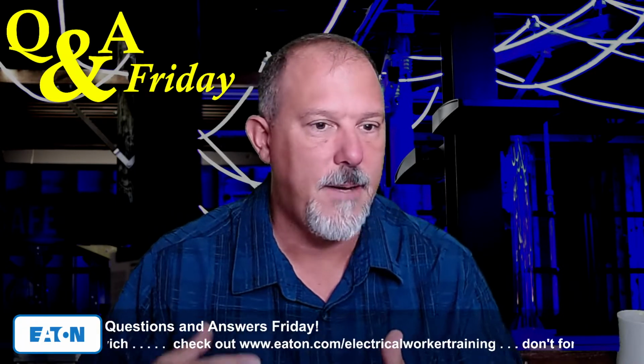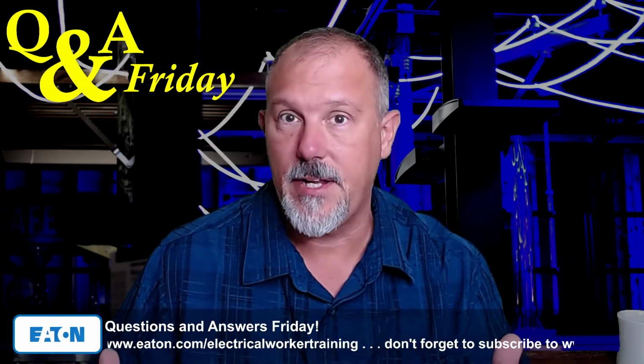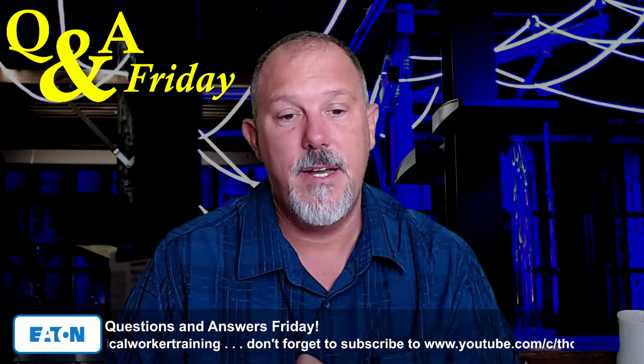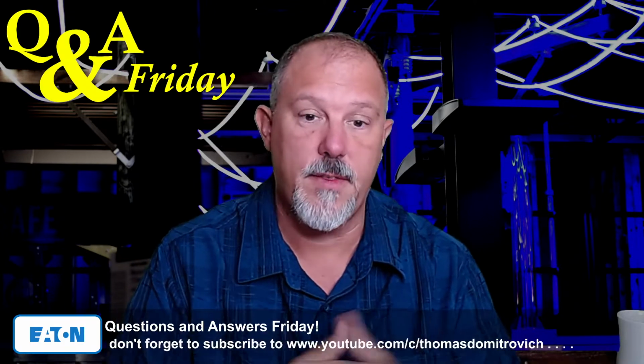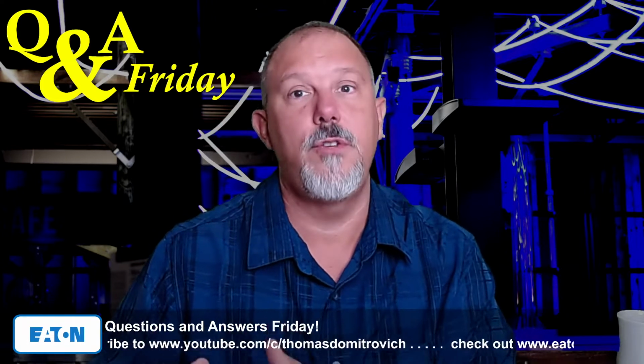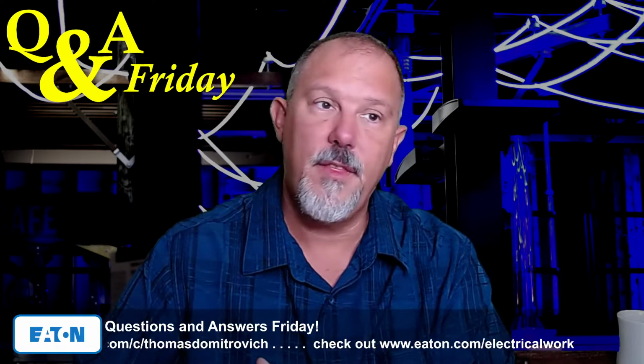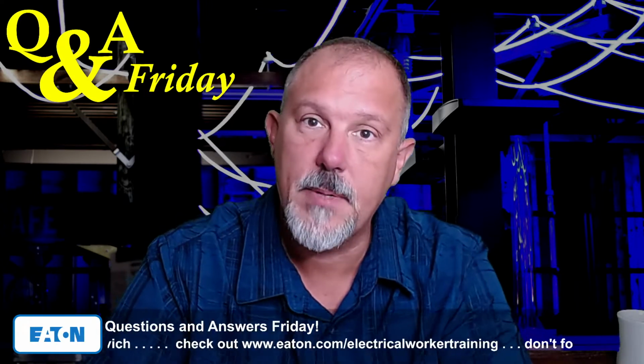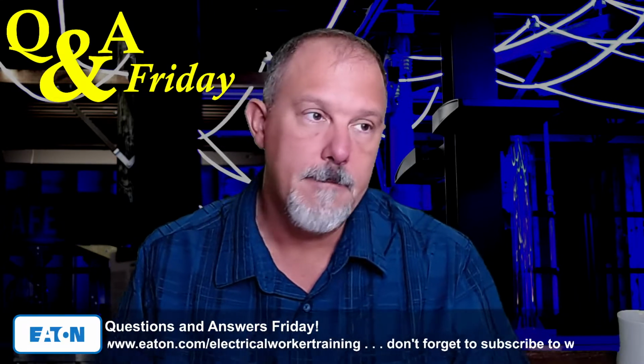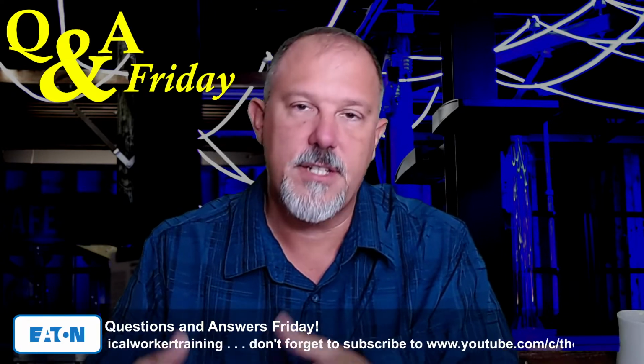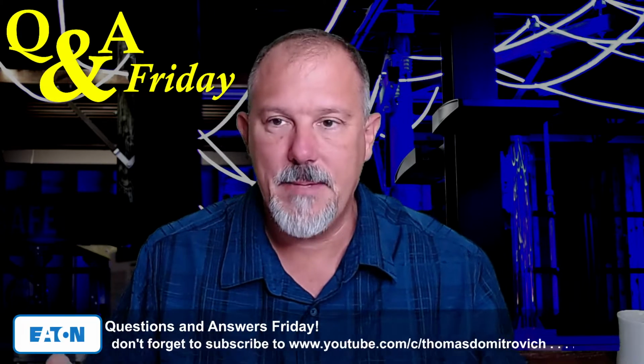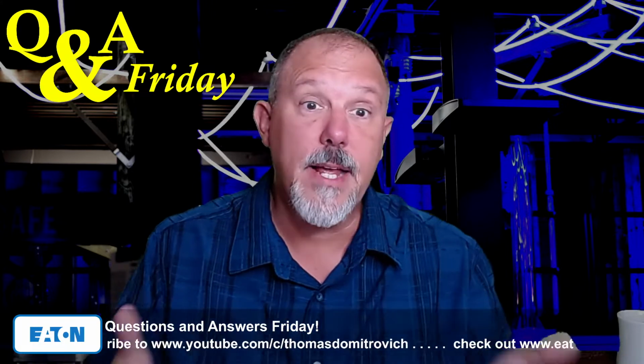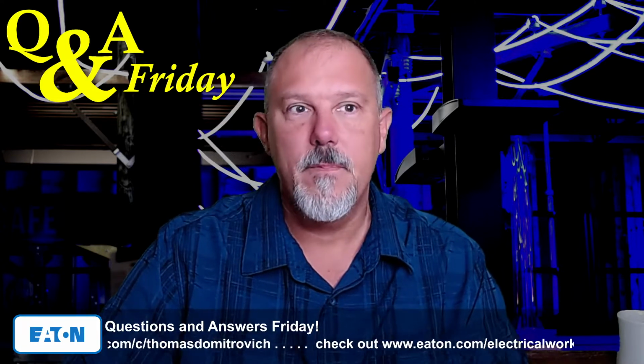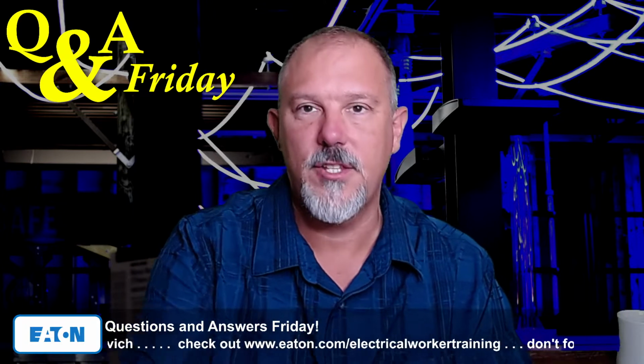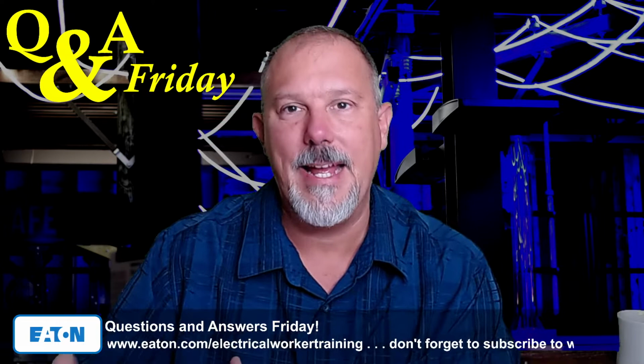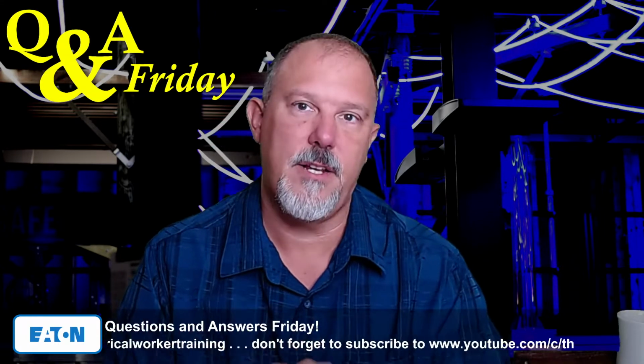So medium voltage is similar in that there's a lot of ancillary components within, whether it be the equipment in the substation, etc., that you need to think about, putting a different thinking cap on and being educated and trained on that equipment. And when you take that medium voltage equipment and put it into a commercial, customer-owned environment, they may have the right contracts in place with qualified people who are going to maintain that equipment appropriately and perform all of the calculations that are needed over the life of the installation. But in many cases, that's not happening. And when you think about the installation, the NESC has a level of awareness of the person who's going to be working on it. So the requirements in the NESC might not be what you would see in the NEC because of the level of expertise that's always around that equipment.